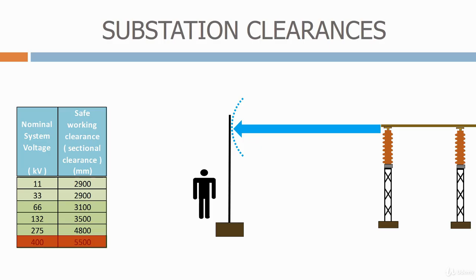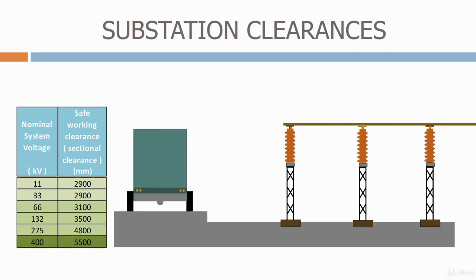By doing this, we've created what's called a safety zone on the other side of the fence. In this area, people can operate safely in the knowledge that they are in no danger from the live electrical equipment. The same stipulation applies where we have a roadway through the substation. The distance from the live conductor to the edge of the roadway must be at least the safe working clearance value.